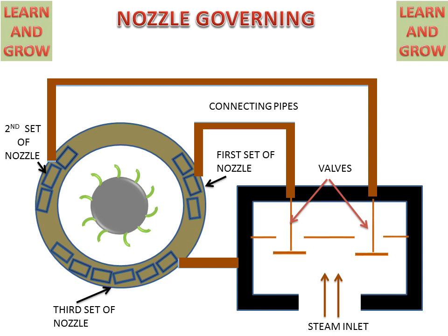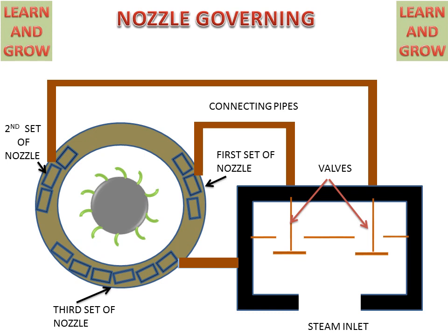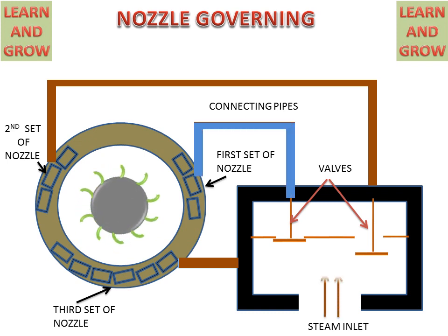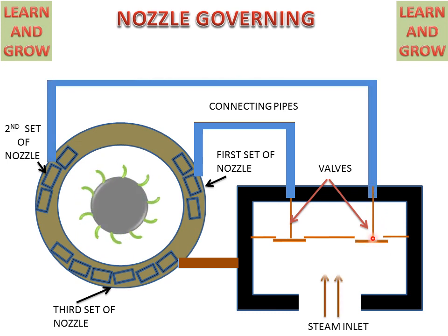In the case of load changes, we can open and close these valves according to the requirement. When steam is at the inlet, we can close this valve, and the supply of steam or water will be stopped, so steam will not go to the first set of nozzles and turbine speed can be maintained. Similarly, the second valve can also be used to stop water or steam going to the second set of nozzles. So from these sets of nozzles, we can maintain the speed of the turbine by opening and closing the valves. This is called nozzle governing.